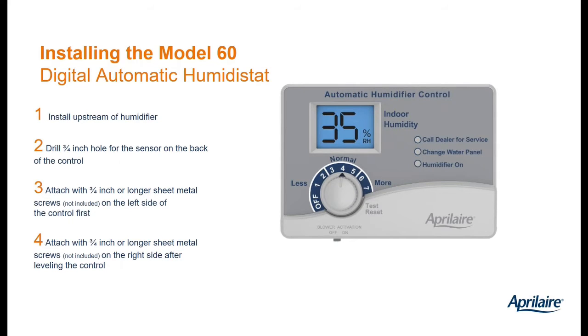The installation is very, very simple. The unit's going to install on the return duct, not in the living space, on the return duct. That's going to let it measure the relative humidity and temperature of the air coming from everywhere in the house that has a return. So it's a good representative sample.